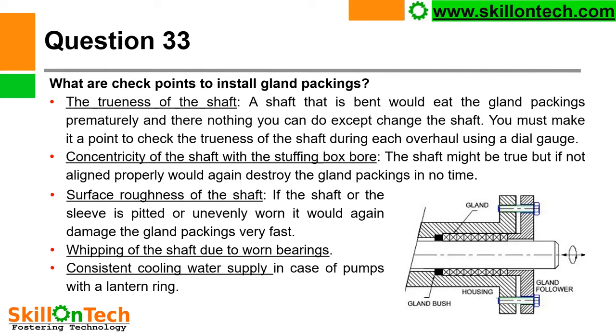What are the checkpoints to install gland packings? The first is the trueness of the shaft. You can see a picture where the shaft, housing, gland packings, gland follower, and bolt are shown. This bolt is used to tighten the gland follower to give tightness to the gland packings. A shaft that is bent would eat the gland packing prematurely and there is nothing you can do except change the shaft. You must make it a point to check the trueness of the shaft during each overhaul using a dial gauge. You can put a shaft in a V block, provide a dial gauge, rotate the shaft and check whether it is bent or not. If your shaft is bent, then you have to replace it; otherwise your gland packing will wear out very fast.